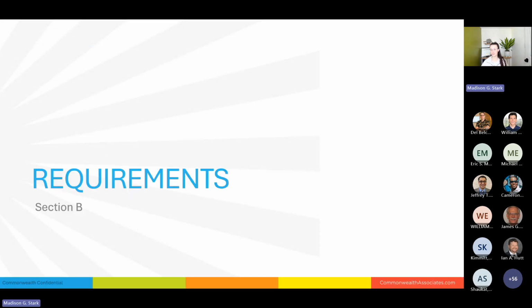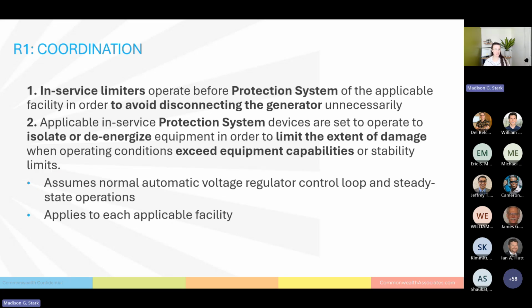So what are the requirements? This is moving into learning objective 2. There are 2 main requirements for coordination under PRC 19. The first regards limiters in the system: the limiters must operate before the protection system in order to avoid disconnecting the generator unnecessarily. A limiter is something that's going to curtail or modify the generator's output to keep it within the generator's capabilities, and we want that to operate so that the generator can stay online as much as possible.